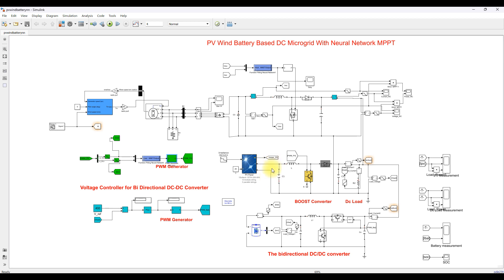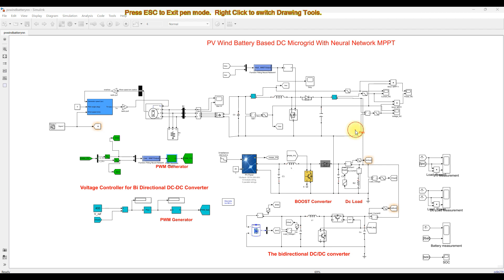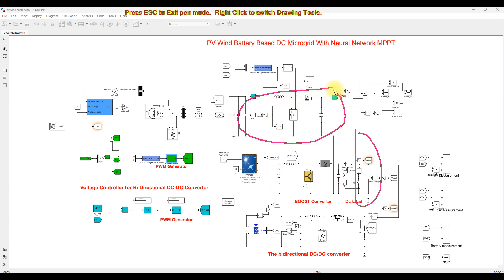The voltage at the PV side is around 245 volts, and in the DC bus we are maintaining around 400 volts. This boost converter extracts the maximum power from the PV array as well as boosts the voltage. Similarly, the wind side boost converter steps up the voltage and extracts the maximum power from the wind turbine and generator.